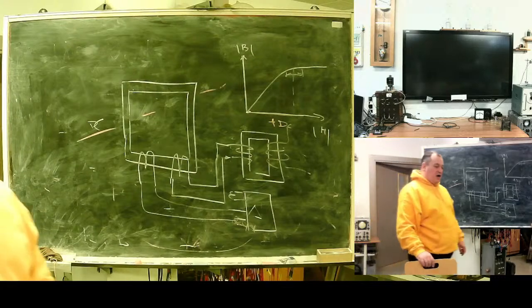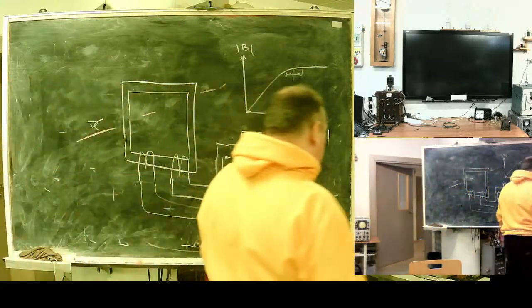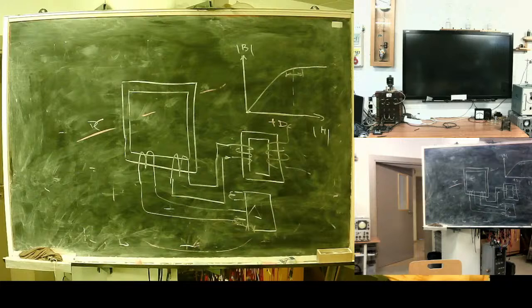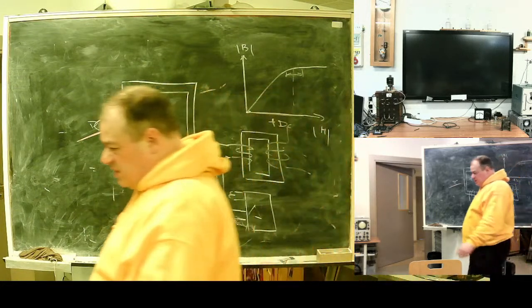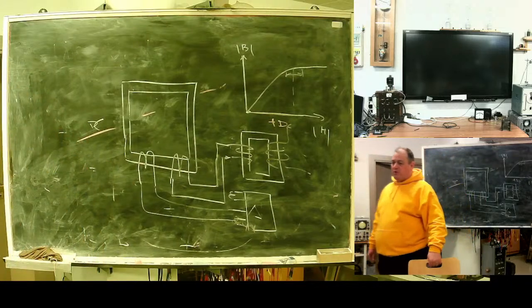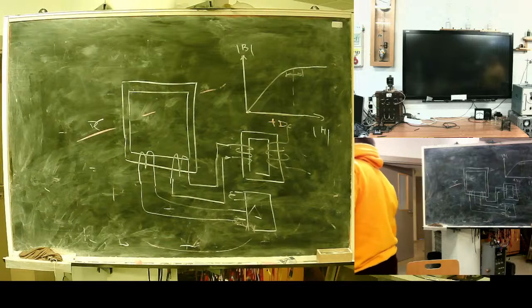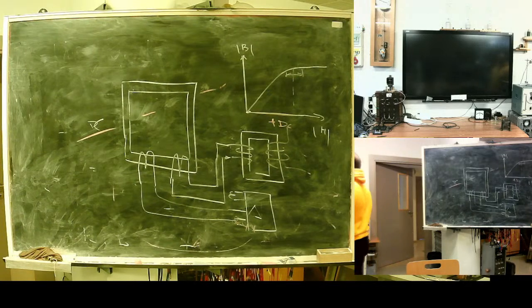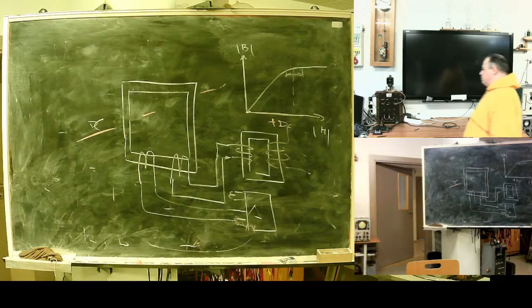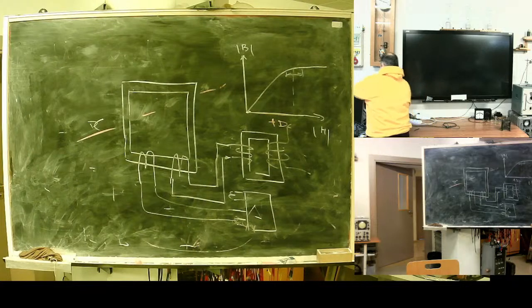They measure current by its thermal effect. Usually it's not a very popular thing in power energetics, but they are used to measure a true effective or RMS current value from excitation inverters.